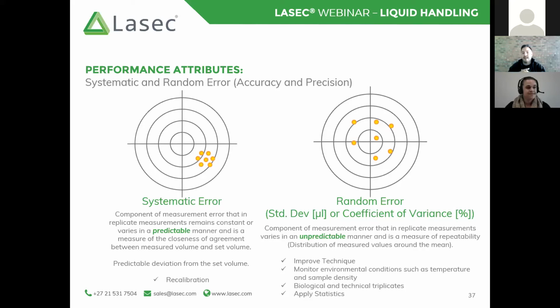The other error is random error. This is also referred to as either standard deviation or, in some cases, coefficient of variance. The only difference between standard deviation and the coefficient of variance is that when random error is shown in terms of a microliter volume or error, it is generally referred to as the standard deviation of those measurements. However, when you convert it to a percentage, we then describe it as the coefficient of variance. So this is basically indicated as the random dispersion of results.